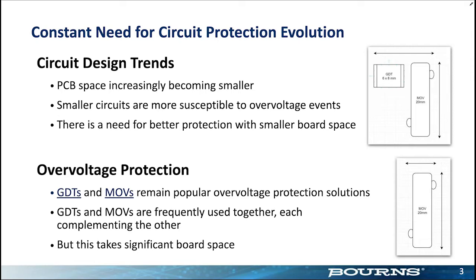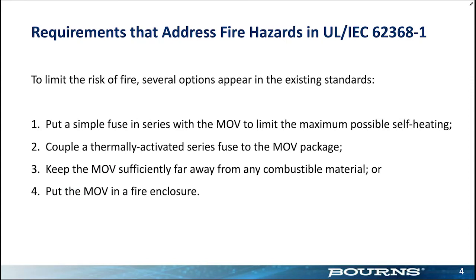of that single MOV. Now, I use the word MOV, and some of you have already tuned me out because you have experience with MOVs. You've been burned by them, both metaphorically as well as perhaps physically. One of the end-of-life phenomena that MOVs can go through is a fairly violent and impressive burst into flame. Not many do it. It's a certain percentage out there, which is small, but billions of these devices are in the field, so 1% of a billion is still a lot of small fires to deal with. So if you don't like MOVs because of that, you'll like what we're talking about today.